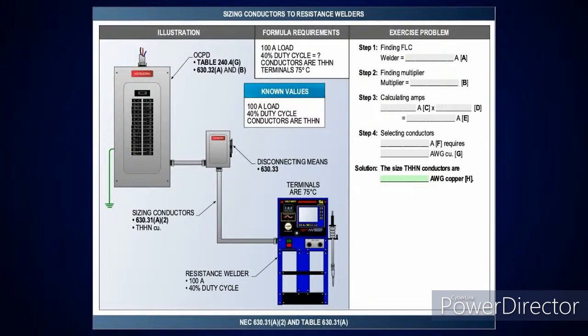And then here we got a 100 amp load, 40% duty cycle. So you should know automatically in step one, it's 100 amps. Step two, I'm looking at table 630.31A, picking up my 40% duty cycle. Get your multiplier, multiply those two together, and whatever your amperage is, you size your conductor based off of that.